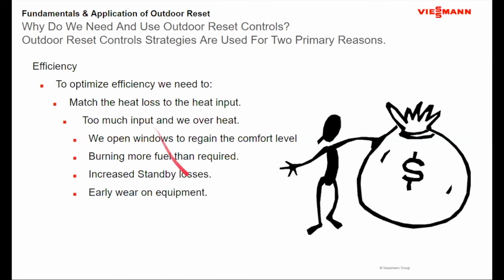I drive my efficiency, I burn less fuel. Also, my standby losses drop as well because my water temperatures aren't as high. I don't turn a pump off and all of a sudden everything's sitting there with 180-degree water, losing this heat that's been paid for. Okay. I'm running constantly at a lower water temperature. The standby losses are less. And because I'm running constantly, there's less starting and stopping, there's less wear and tear on the equipment.